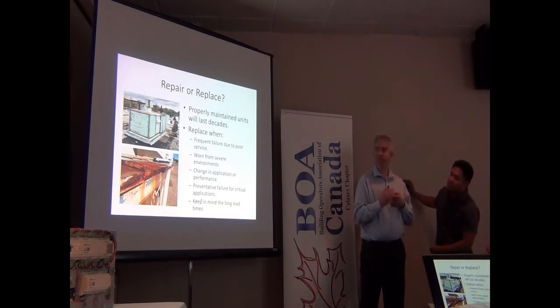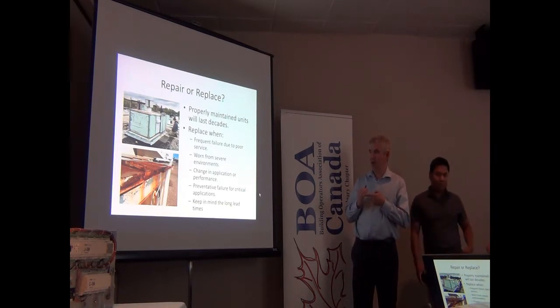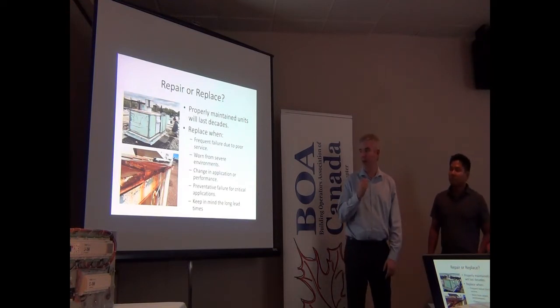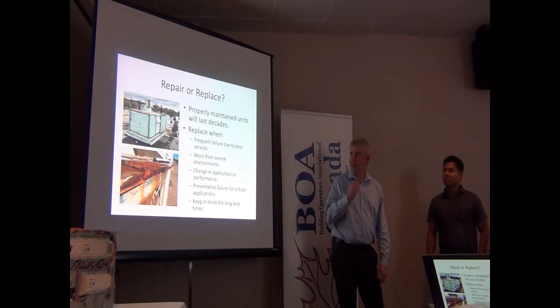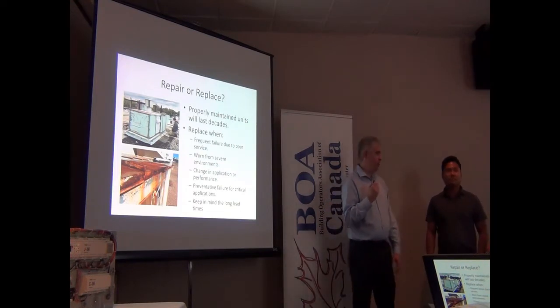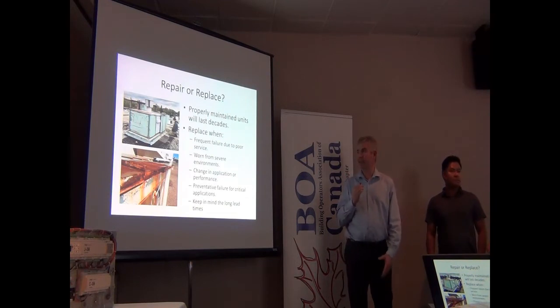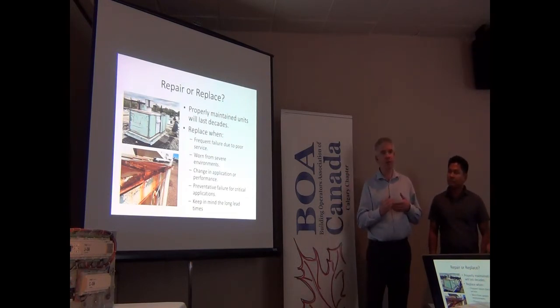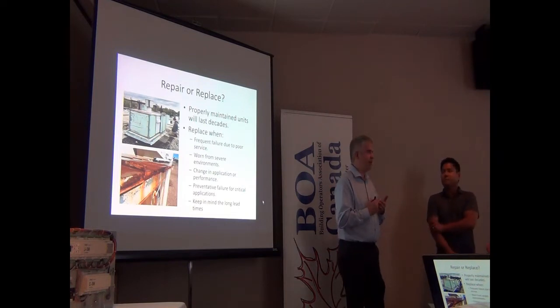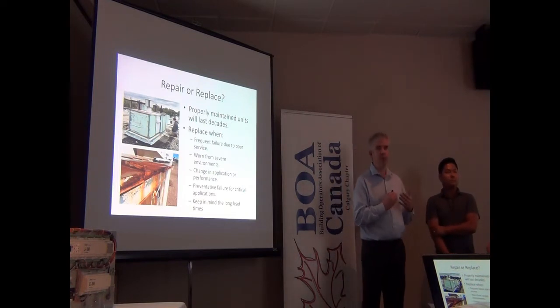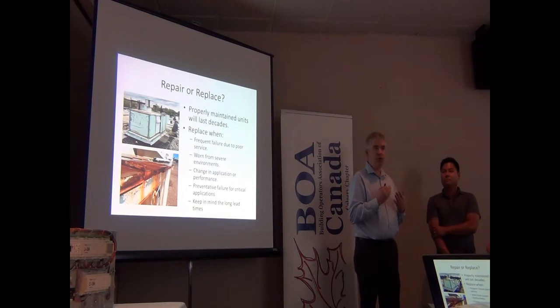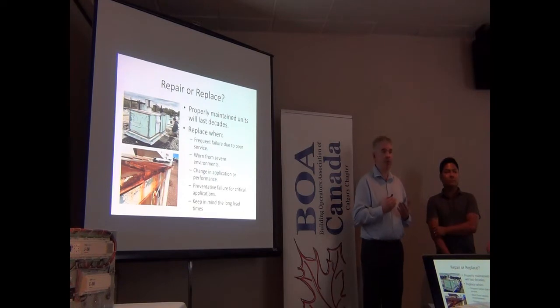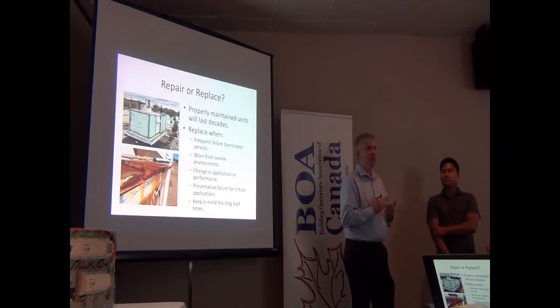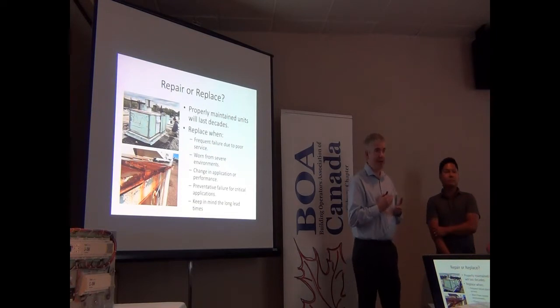So if you take a look, there's a picture of the unit at the bottom. I think that one's operating in a potash environment. That unit is only 5 years old, I want to say. So depending on what environment it's in, it can drastically change the lifetime of your unit, or change your usage scenario. If you have a unit that's turned on only during occupied hours, and it's only recirculating air in a space, with very little outdoor air, it might not have a huge load on it for its whole life. It may not be running 24 hours a day. Versus a makeup air unit that's running 24 hours a day, every day of the year, where the lifetime of those components could change drastically.